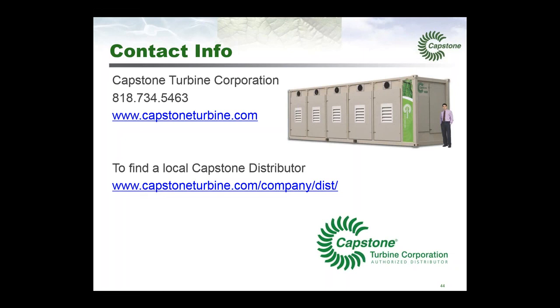Can you discuss utility standby rates and tariffs and how that affects feasibility? It can have a significant impact on project payback. When we model a project, we do take all those factors into account. Typically, the bulk of your savings is going to come from reduced kilowatt hour purchase and reduced demand charges over time. Because of the modularity of our system, demand charges are pretty easy to get away from because any maintenance event only takes out part of your array if you have 12 C65s or 5 of the 200 kilowatt machines.